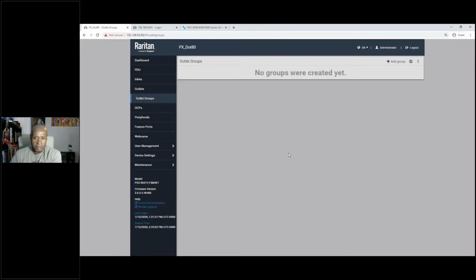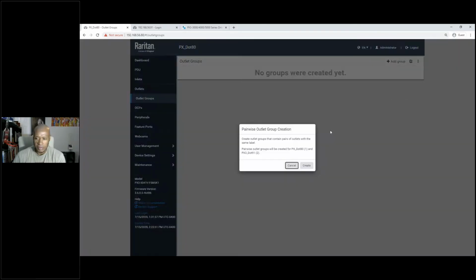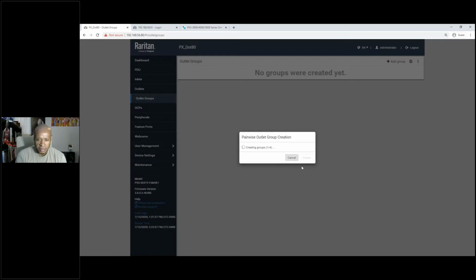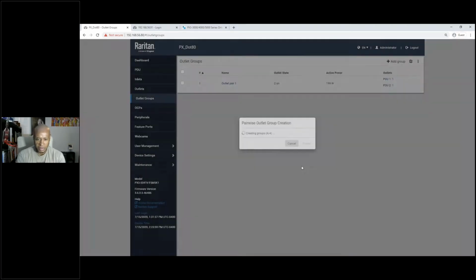This will require firmware version 3.6, and it will require some PDUs to be linked together before you see this. But if you go to outlet groups and click on this icon to the very far right here, you'll see automatic creation. Once that's clicked, the pairwise outlet group pops up. So you see 1 and 2, hit create, and it automatically generates those four groups.